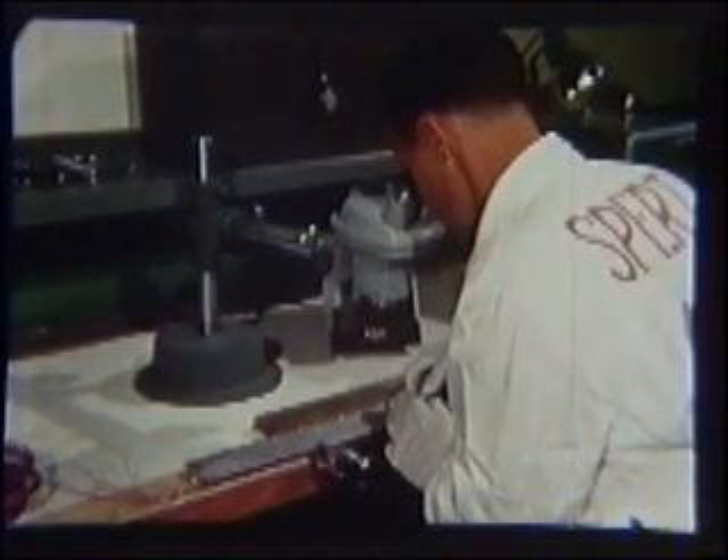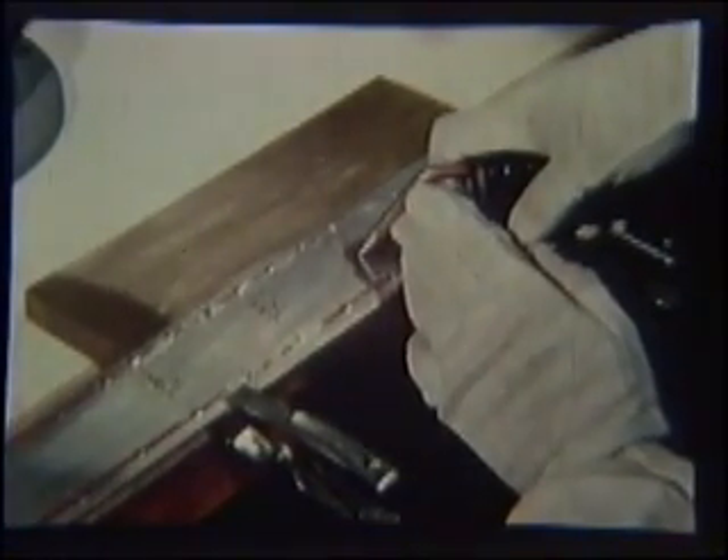In the destructive test series, several types of devices were used to measure temperature, power, and pressure. The temperature measurements were obtained by means of thermocouples, some of which were mounted on the surface of various fuel plates, and others buried in the fuel plate cladding.